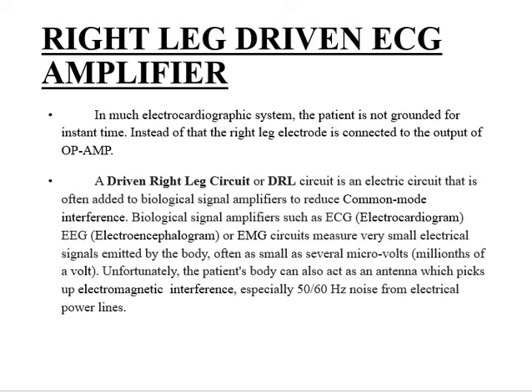It's very simple: take that reference electrode and place it on the patient's body. Instead of placing it in some other location entirely far away from the patient, if you place that reference electrode near the patient or on the patient, then there is no chance of neglecting any waveform or any output. We can take even very low amplitude and very low frequency into consideration for analysis purposes. That is why the Right Leg Driven ECG Amplifier system is introduced.